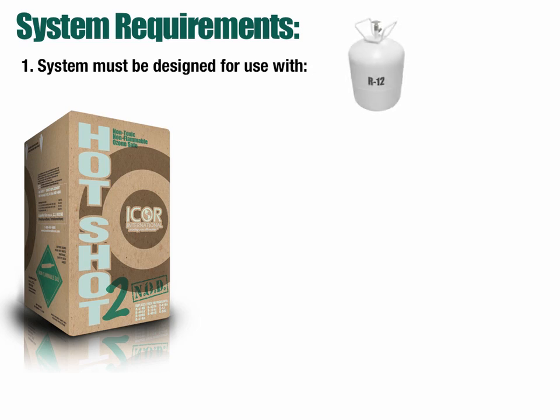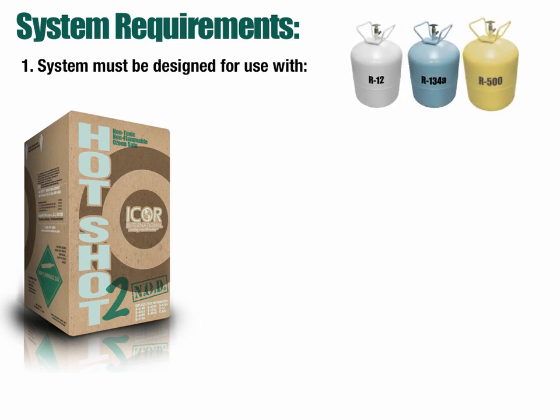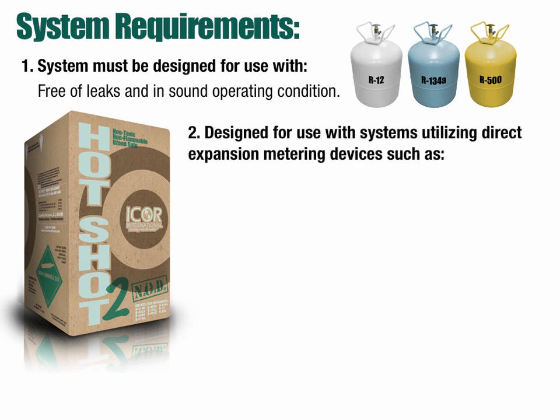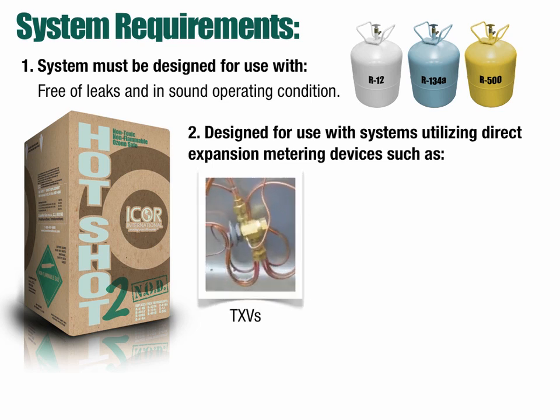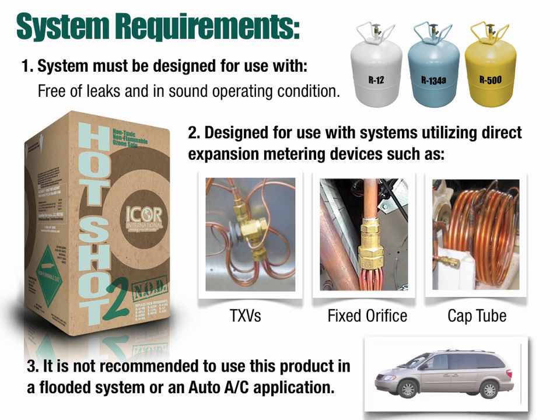ICOR recommends following these three requirements when considering retrofitting to Hotshot 2. 1. The system must be designed for use with R12, R134A, or R500, free of leaks and in sound operating condition. 2. Hotshot 2 is designed for use in systems utilizing direct expansion metering devices such as TXVs, fixed orifice, or cap tube. 3. It is not recommended to use this product in a flooded system or an auto-AC application.